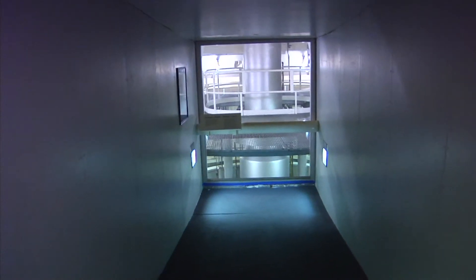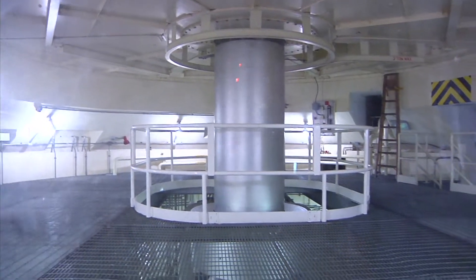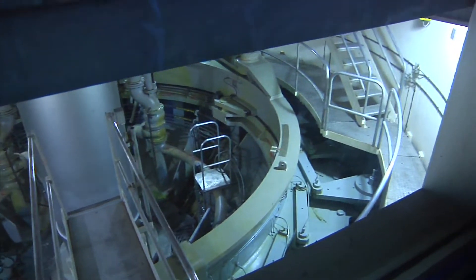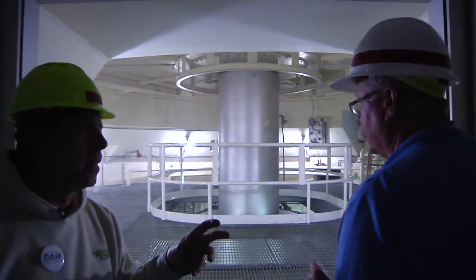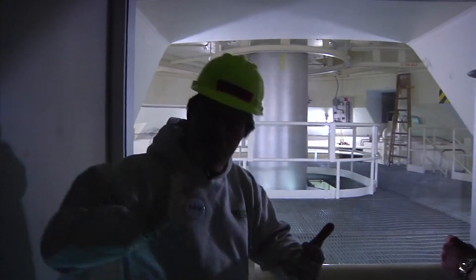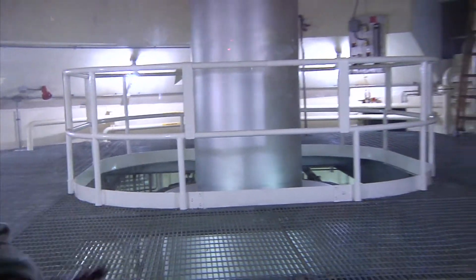Here's an opportunity to look inside the turbine pit — you can see the turbine shaft rotating. This is where we control the amount of water that goes over the turbine using the wicket gates and operating ring; the hydraulic system regulates water flow on the turbine shaft. The actual spindle in the center stays at a constant 75 revolutions per minute. If more water is introduced into the system, the spindle still maintains its 75 RPM, but more torque is then pushed onto that spindle.